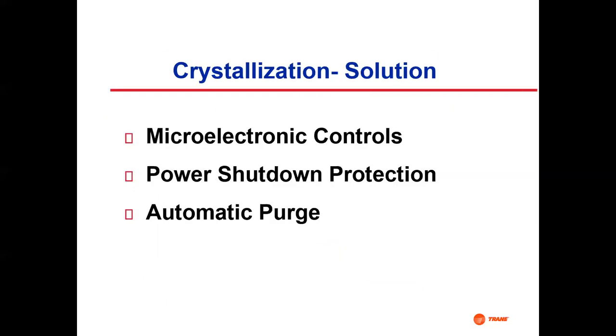This has gotten much better. We have automatic purge; it can sense when air is in the machine, and they go ahead and suck it out and get rid of it automatically as part of the cycle. Shutdown protection: they design the machine so that on a power failure they're less likely to have that problem. And of course, controls are getting much, much better.